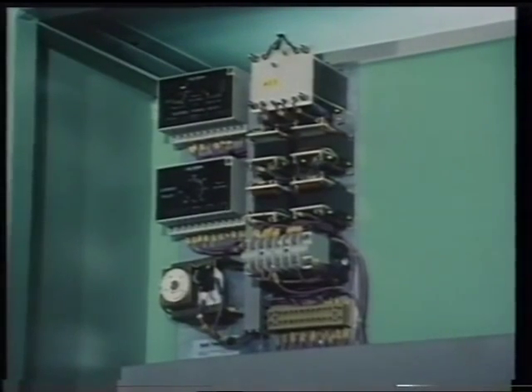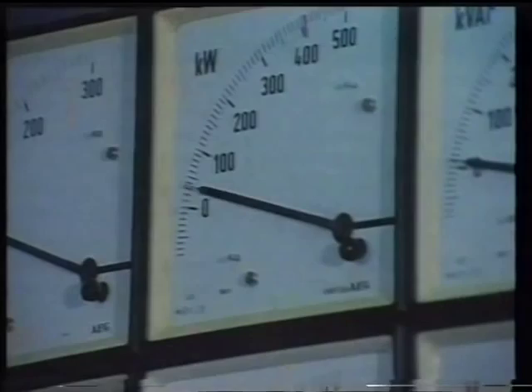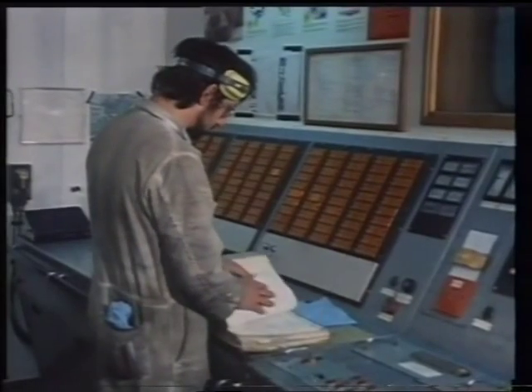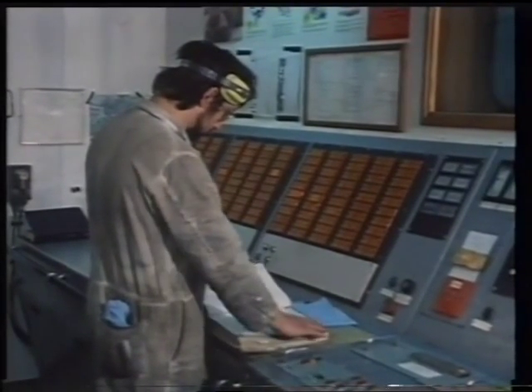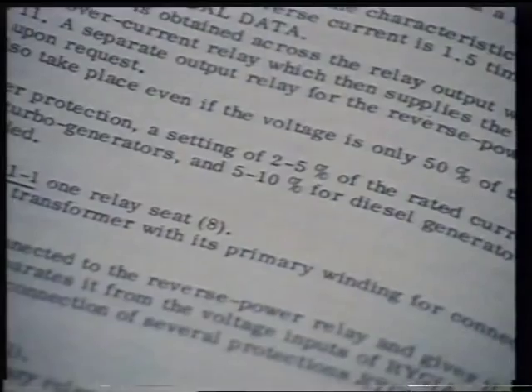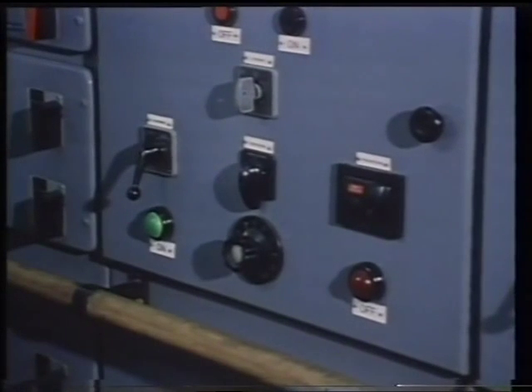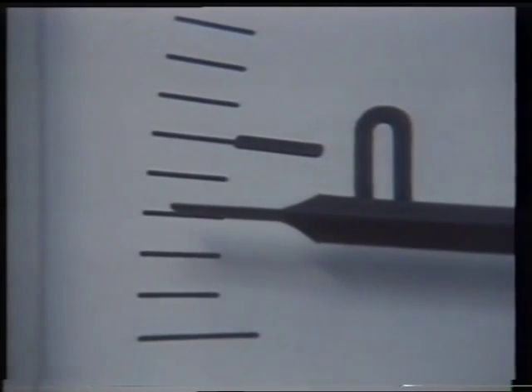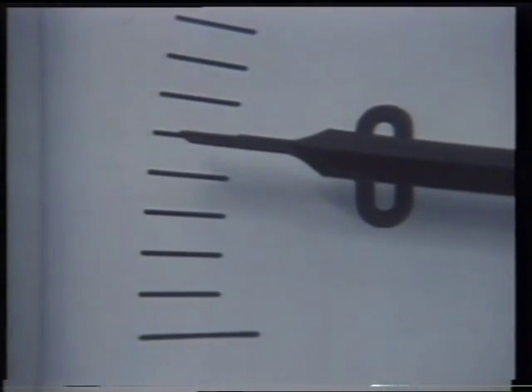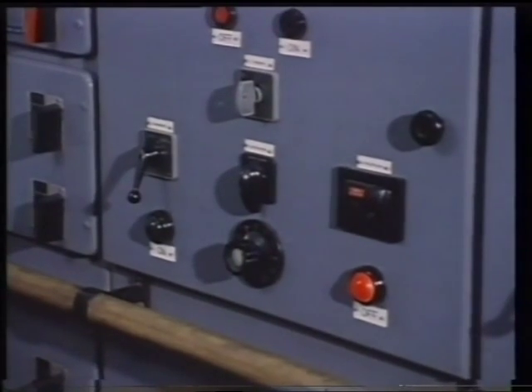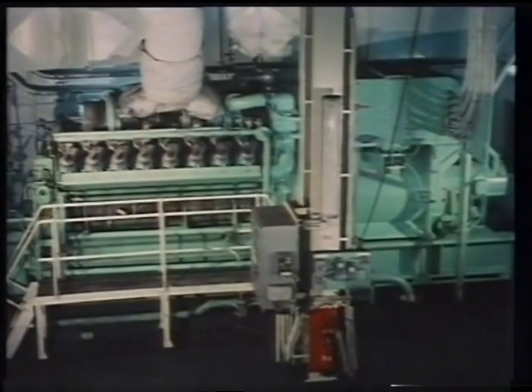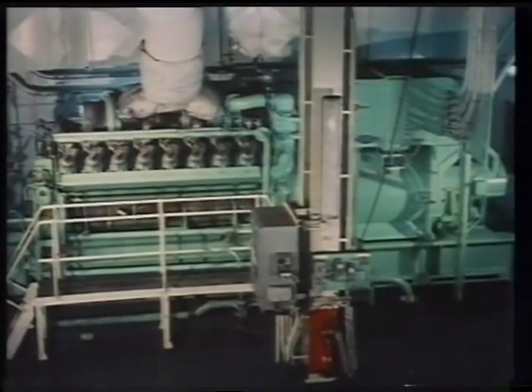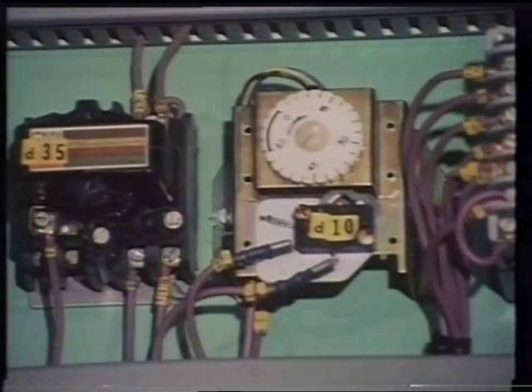The reverse power relay must be checked periodically by reducing the speed of the prime mover until the reverse power relay has operated. This point is preset at a few % of the full rated generator output. The settings are different for diesel or steam turbine prime movers. If, for any reason, the reverse power unit of an alternator malfunctions, the alternator must be under constant watch while running in parallel. The preferential trip relay will shed non-essential loads if the alternator is overloaded until normal load condition is reached.